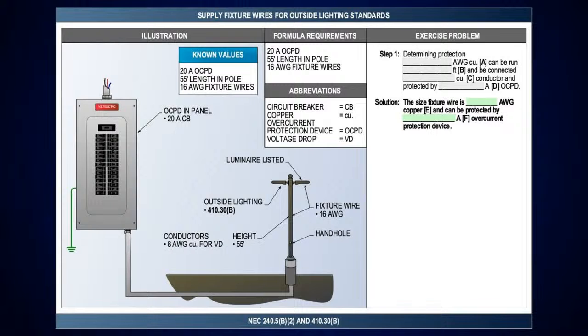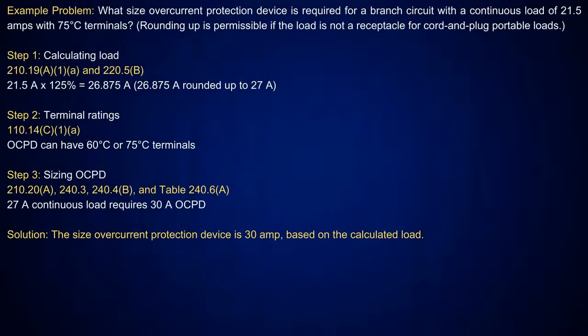Well, looky here. We're making you think here, because I'm going all the way over here, and I had to upsize those conductors due to voltage drop, and I've got a number 8 conductor. Can I do this? You see what I'm saying? So you got to go look at 240.5(B)(2) to make that determination. Okay. Yeah, and you'd have to bond with the number 8 minimum conductor too. Right.